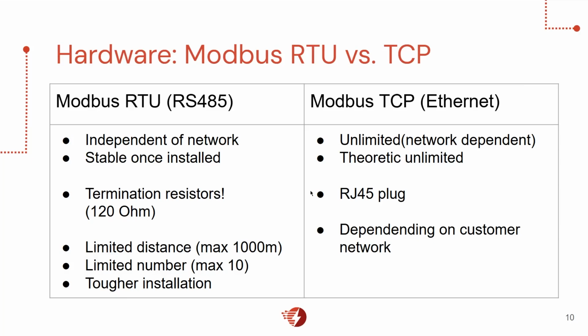So it's the RS485 connection between the box and your asset. This is a wired connection, so it's always stable. Do keep in mind that we have resistors of about 120 ohms at the end. I will come back to that in just a second. It is limited in distance as well. The maximum distance you could go in practical terms is about 100 meters. We also have a practical limit on the number of assets you could connect, about 10 pieces before there's too much noise on the chain, which makes for a more difficult installation process.